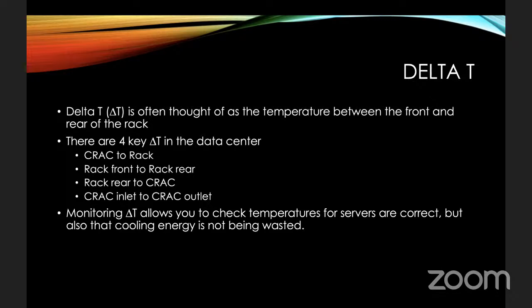There is the CRAC to rack. So that is, what is the temperature difference between the air exiting your CRAC and the air entering the rack? You then have the delta T that everyone thinks of, which is the rack front to rear. You then have the rack rear to the CRAC inlet. And you also have the delta T across the CRAC, that's from the inlet to the outlet. So monitoring the delta T allows you to check the temperature for the servers is correct, but also that the cooling energy is not being wasted and is being used efficiently. I'm going to go into more detail now about that.